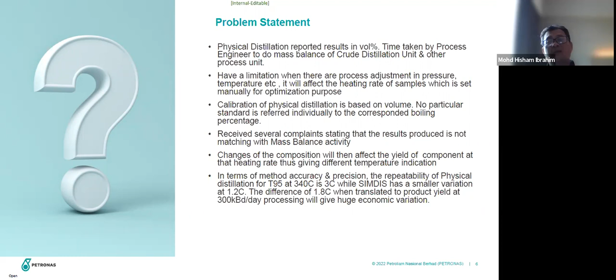Okay, the difference of 1.8 degrees C translated to product yield at 300 kilobarrels per day processing will give a huge economic variation. Right. So the objective of this presentation is to determine the process streams for a feasibility study in developing the correct correlation equations. What we did is to do a test run of the identified process streams. We identified the test run offset value as a common value for all streams, and determined the correlation study between D86 and the simulated distillation as the first stage of the study, which is to find the correlation factor, collect the data, and draw the baseline.